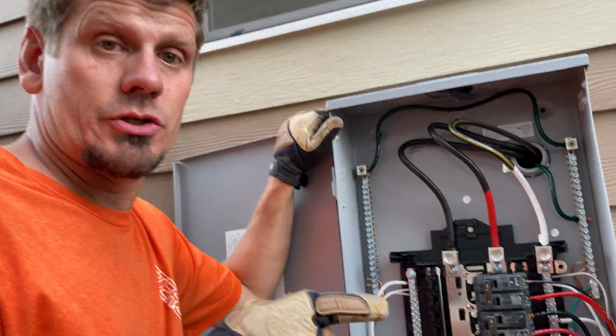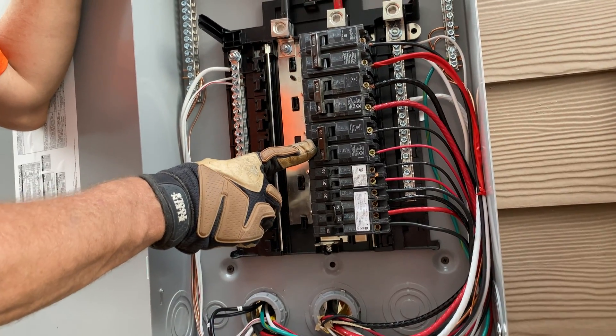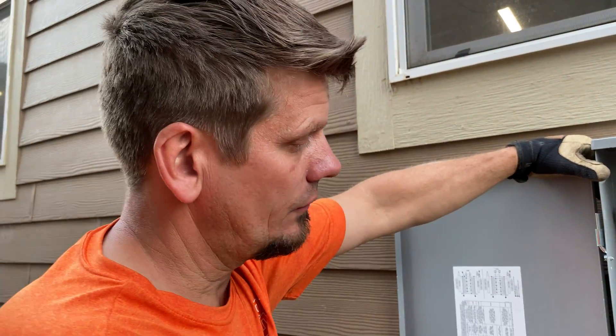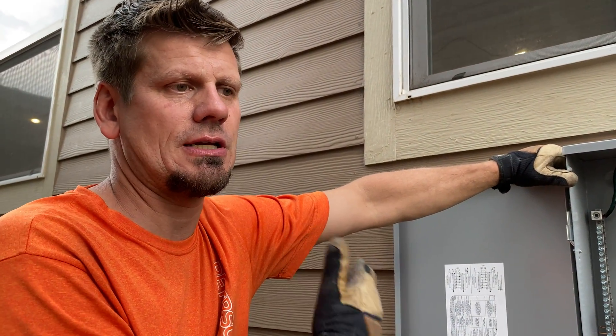They still don't have a dual-function multi-tie that shares black and red. They do have a dual-function only black or dual-function only red, of course. But pulling through — this would be one, two, three spots, and if they want to be really strict on me, surge protection or my heater — that could be one, two, three, four, five. At $150 a breaker — that's $750, maybe $800 with tax. Five GFI breakers. Again, if you don't have the full bus bar space and you have quads or twins, you're screwed. You need to set another sub panel just to fit these GFI breakers.